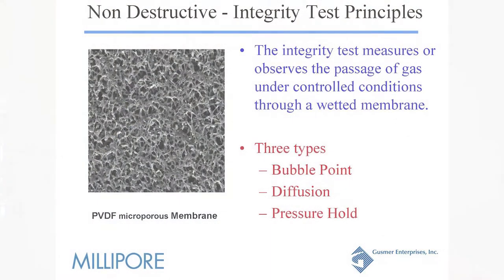This is a picture of the PVDF membrane. It's important to realize that it is not a bunch of holes poked into a piece of paper — it is layers of filaments on top of each other. When you say 0.45 or 0.65 or 1.0 micron, it's not that there's actually a pore size that big. It is actually saying that that membrane will retain whatever that micron rating is. They do a physical challenge with particles the size the membrane should retain. It's a treacherous path in that membrane — as Nate mentioned, it's about as thick as a piece of paper. The critter or particle enters that membrane, gets stuck in the center, and can't go forward or backwards.